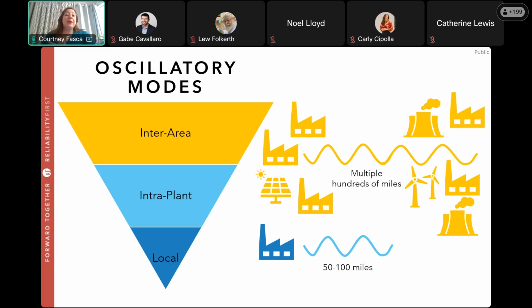So you may be wondering, how do we dampen these oscillations? Is there a difference between how we handle them depending on what mode they are? So for the local modes, a single properly tuned PSS can effectively damp local oscillations because, again, it's usually one generator or a few closely located machines. Meanwhile, if we're looking at inter-area mode damping, that requires coordinated control of multiple PSSs because now we have multiple generators that can be across different areas, and the added complication that individual PSS actions can actually reinforce or cancel each other out, depending on the relative participation in the inter-area mode.